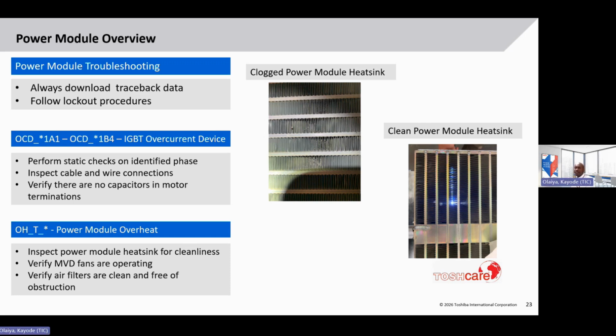Next step is to lock out the drive. Follow your lockout procedures to make sure that the drive is isolated. So first fault there is the OCD, overcurrent device. And it follows the format shown there. The asterisk refers to the phase that is affected. So it'll be U, V, W, and that's starting from left to right if you're looking at the front of the drive. And it goes from A1 to B4, which is A1, A4, B1, B4.